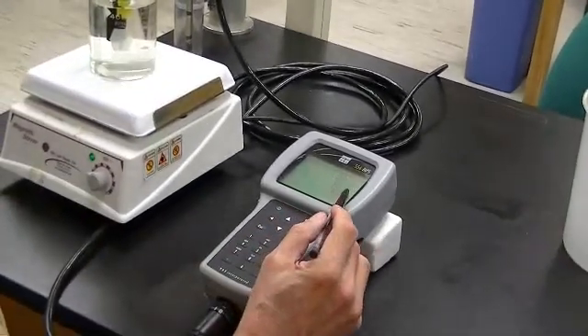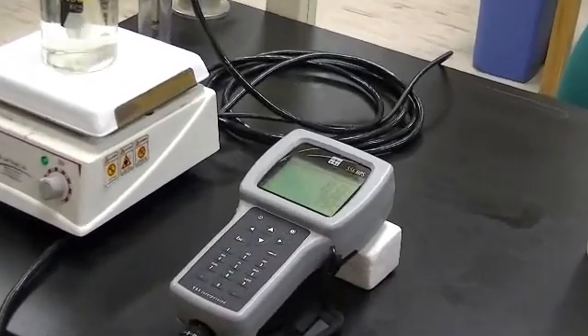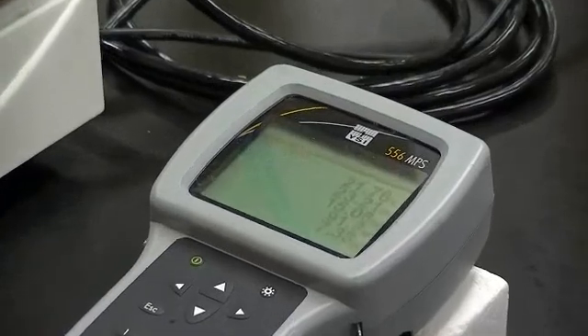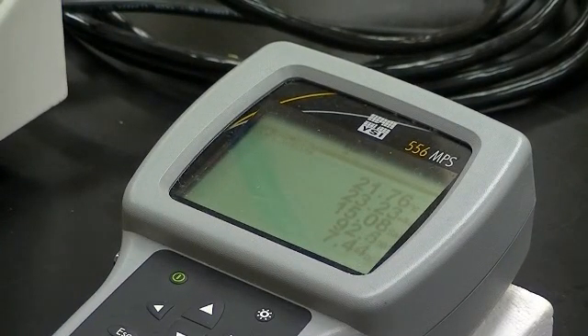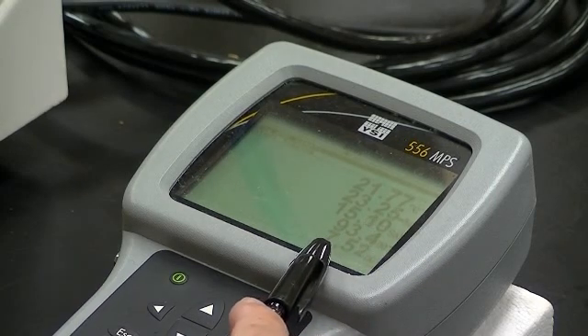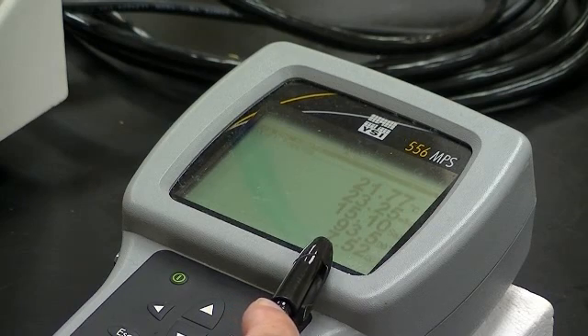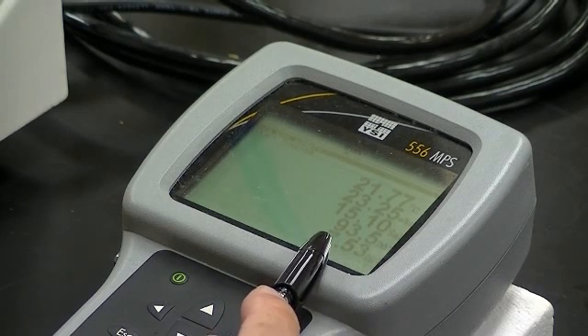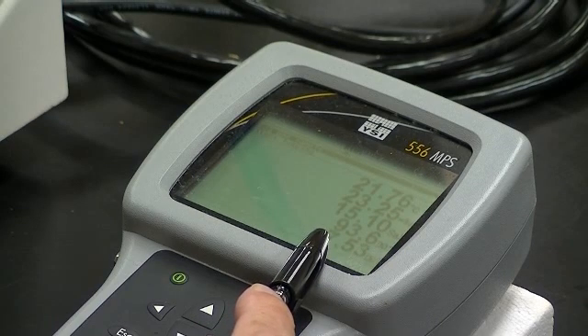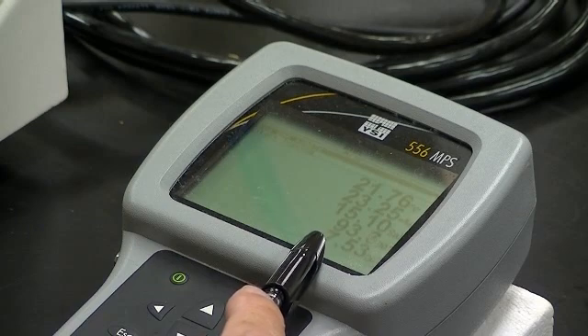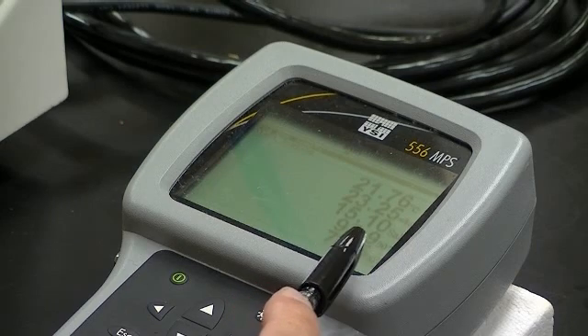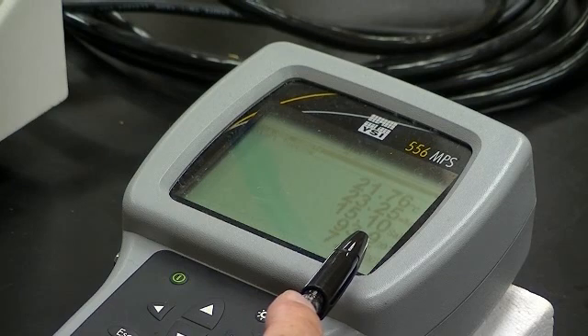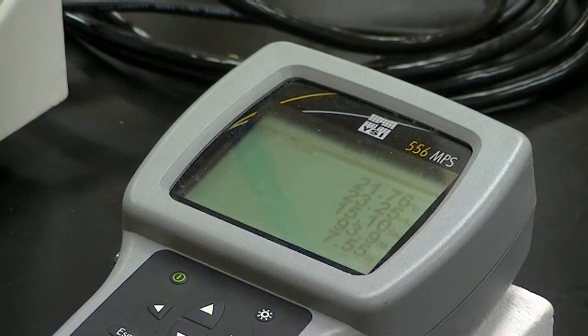All right, so now we just wait for the display to settle down. Now this water's been in that jug for a long time, and I'm not exactly sure what the oxygen concentration is going to be. So we're finding out right now what it is today. Now you're looking at the bottom number, and this says 7.52, 7.53, 7.53, 7.54, 7.55, all right, we'll call it 7.55.